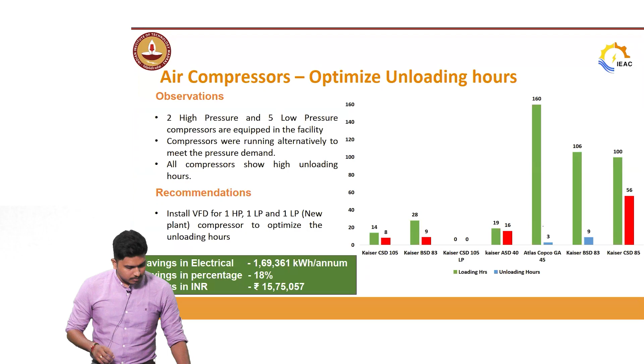There is one thing called a variable frequency drive, or VFD. These VFDs can be installed for the compressor motors, and they provide the right amount of speed so the motor delivers only the required power, running only when demand meets it. By this technology, we can save around 15 lakh rupees and 1.7 lakh units per annum.